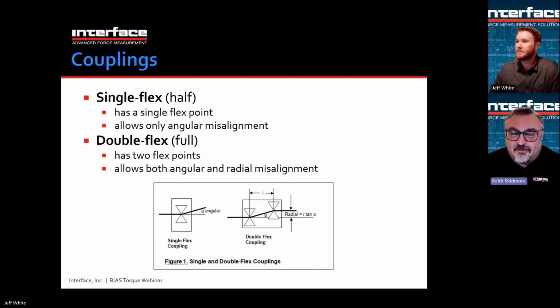So we have different types of couplings. A single flex or a half coupling has a single flex point, and it only allows angular displacement. And then a double flex or a full coupling has two flex points and allows both angular and radial misalignment. As you see in the bottom left here, that's a single flex coupling on the left, and it only has an angular displacement capability. Now, if you take two single flex couplings, which we also call half couplings, and mount them together, it becomes a full coupling or a double flex coupling.